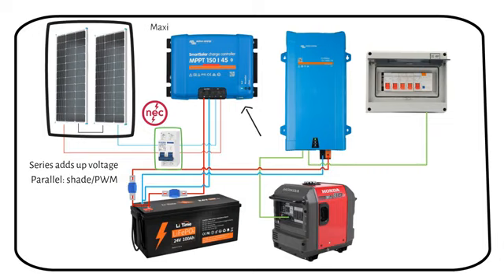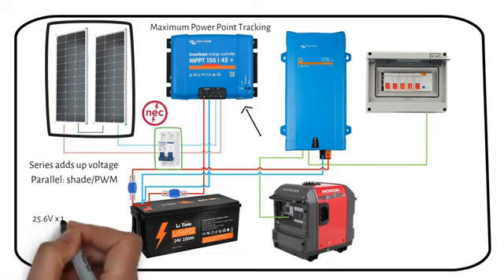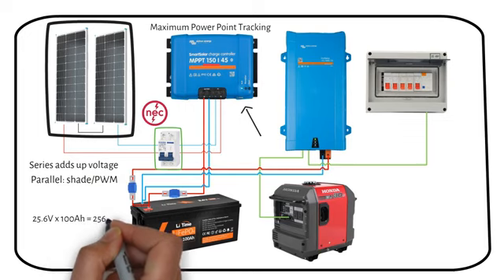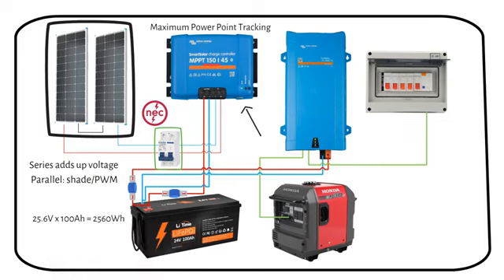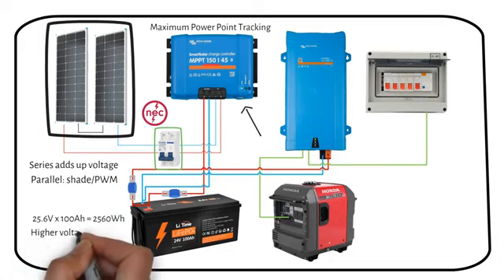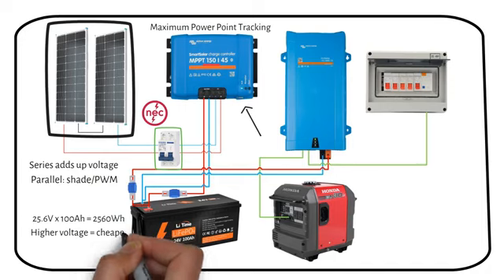MPPT stands for Maximum Power Point Tracking, a technology that gets the most power from your panels. The battery is 24 volt lithium iron phosphate. It has a higher voltage and more capacity than the battery in the previous system, meaning it can store more energy and provide power for longer periods. Increasing the voltage of your battery allows for a cheaper charge controller, cheaper wires, and a cheaper battery charger.